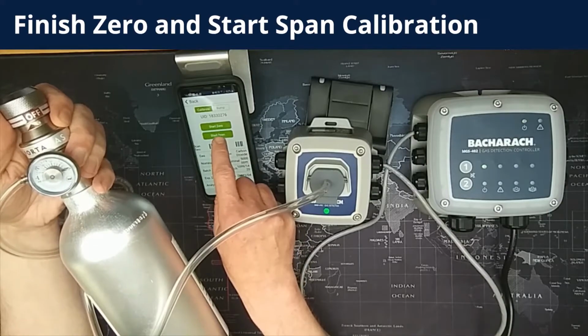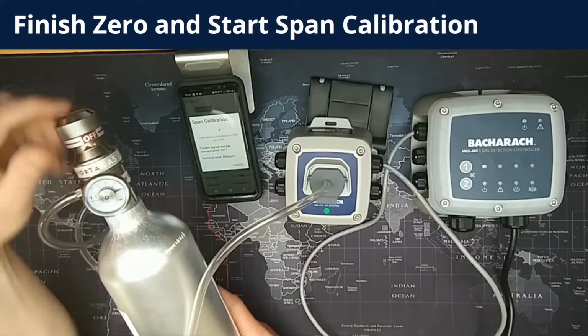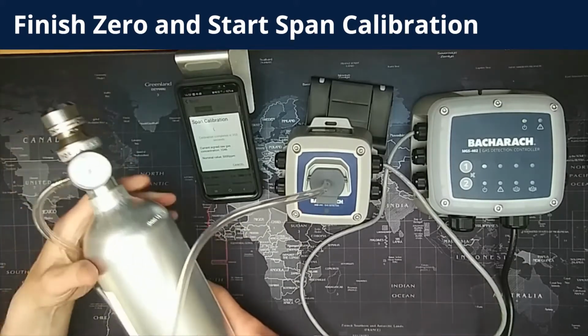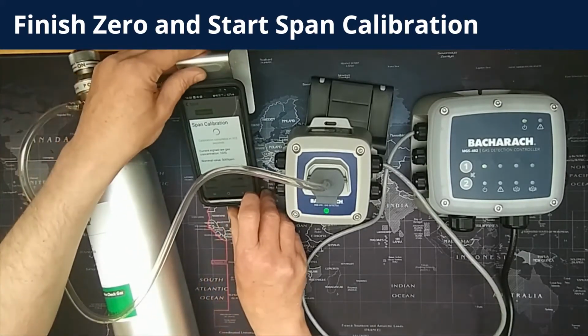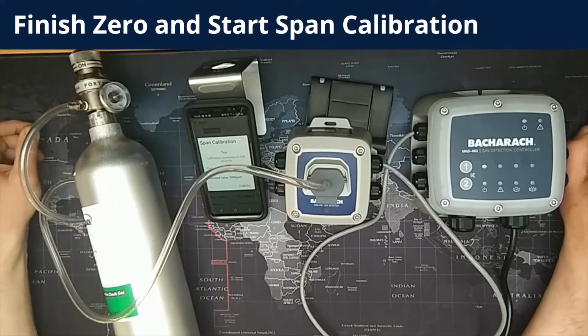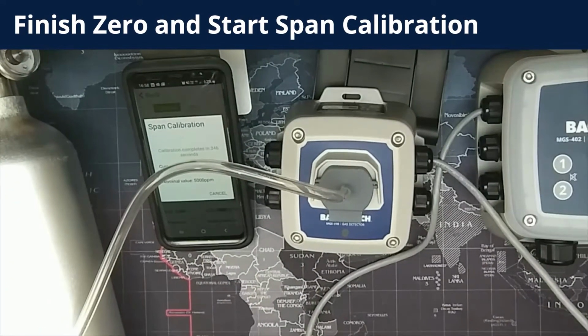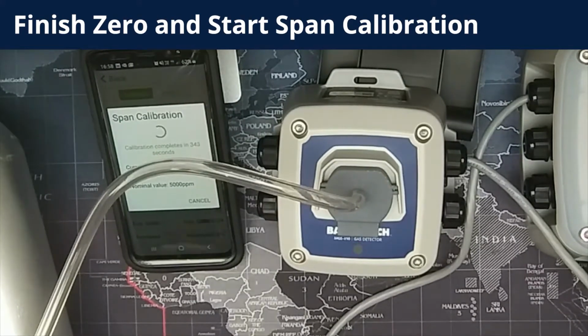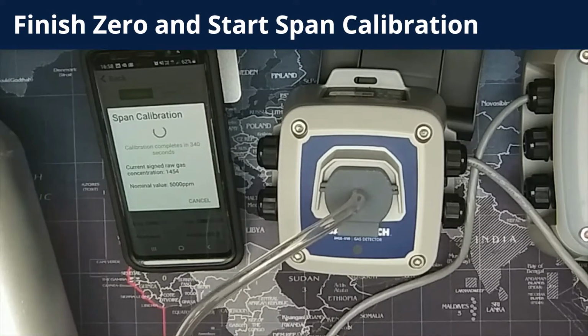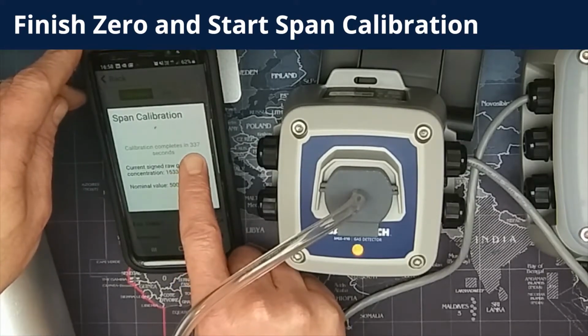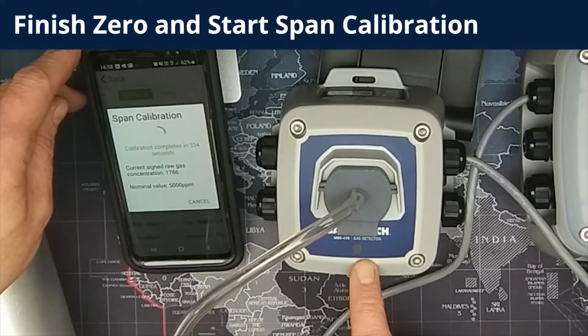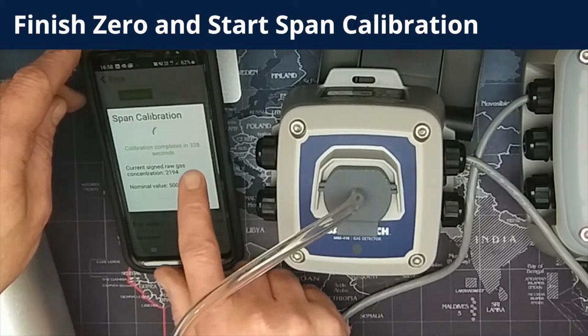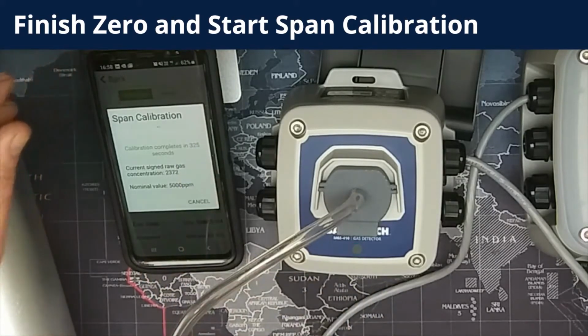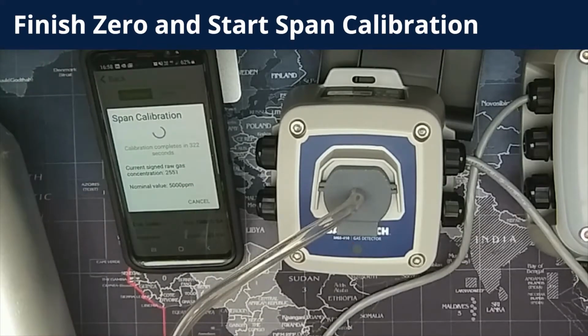Fit the calibration adapter again. Then you want to select Start Span. It will start the countdown, and you need to turn the regulator on to allow the span gas to flow to the detector. So you'll be able to see on the phone screen that it is counting down, and also note that the LED on the device is going through a color sequence. That color sequence again is detailed in the manual. So there is the countdown counting down on the app. The LED is changing and you need to wait for the countdown to reach 0 seconds.